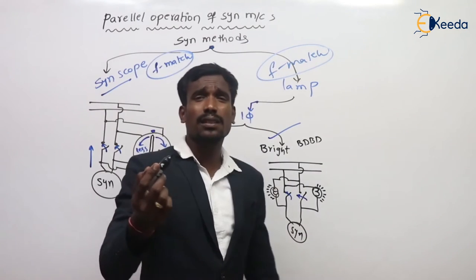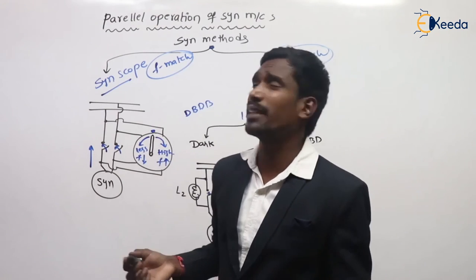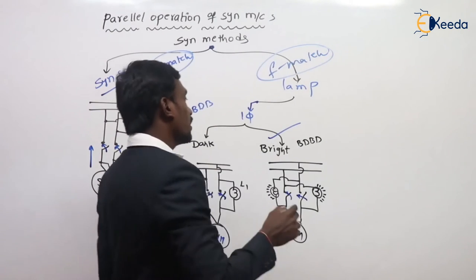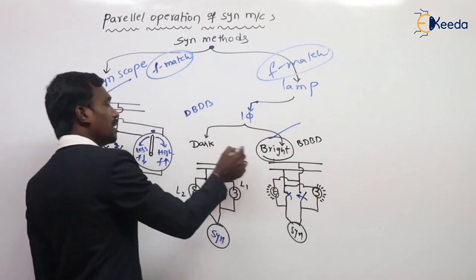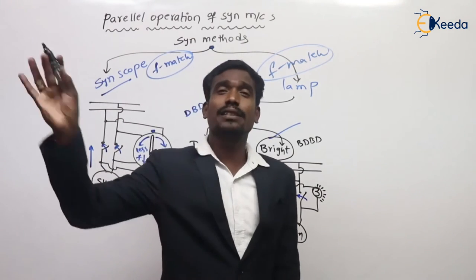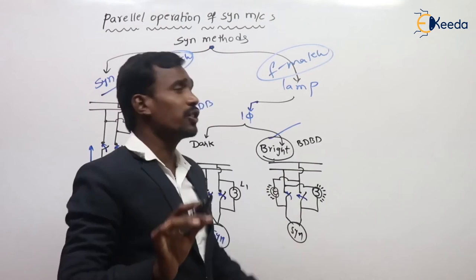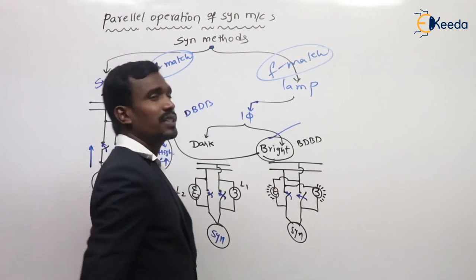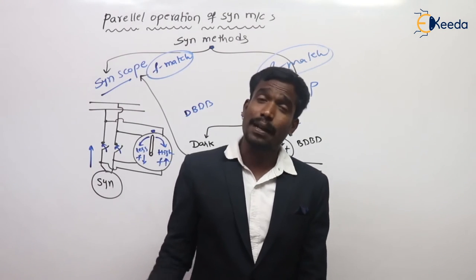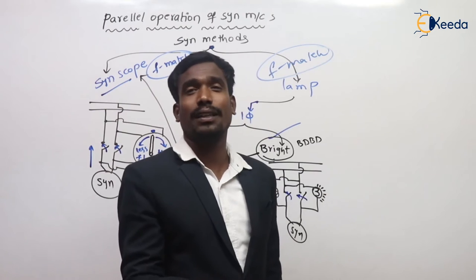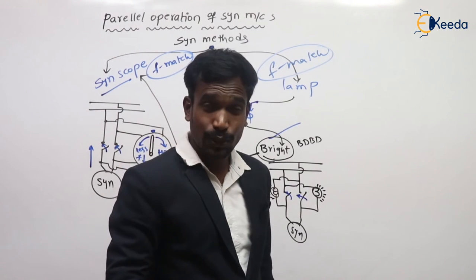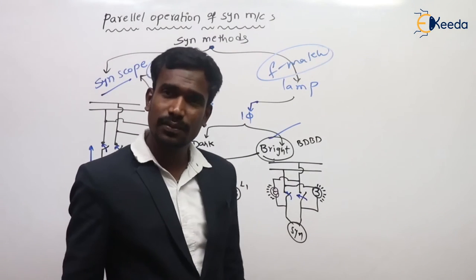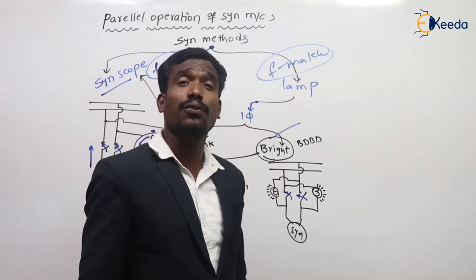The answer to which method we use today: generally the bright lamp method is better than the dark lamp method because of easy judgment. Nowadays we use the bright lamp method in combination with the synchronoscope method — bright lamp method plus synchronoscope method combined. This completes the synchronization method for single phase. Let's go to the synchronization method for three phase.